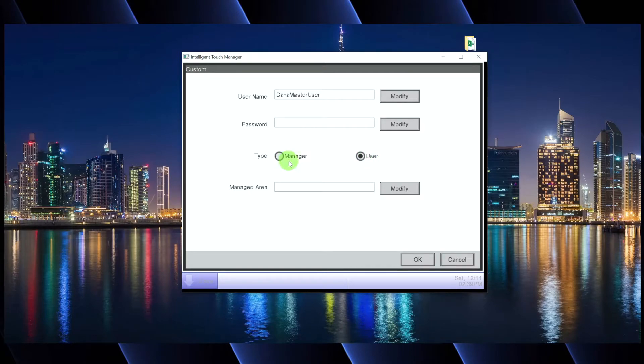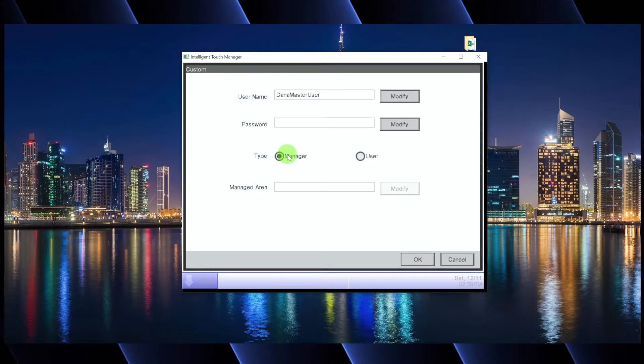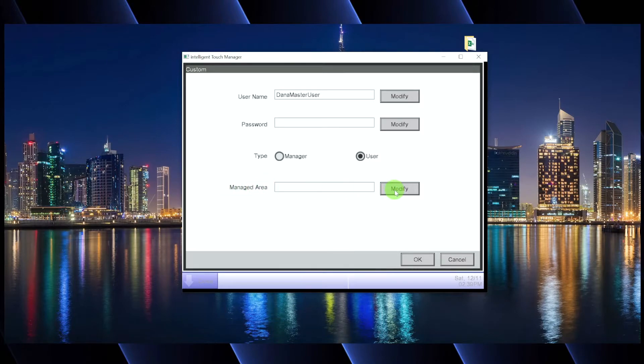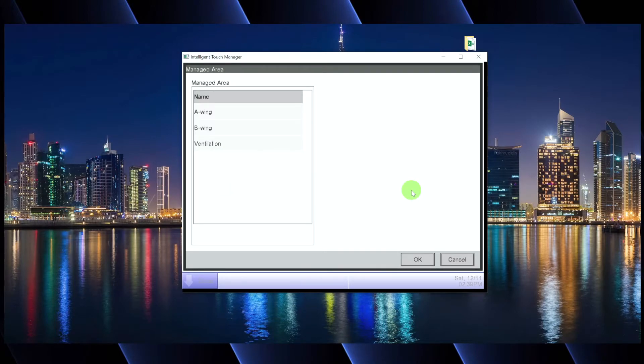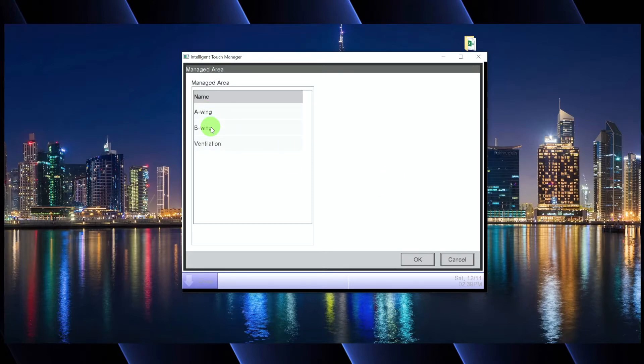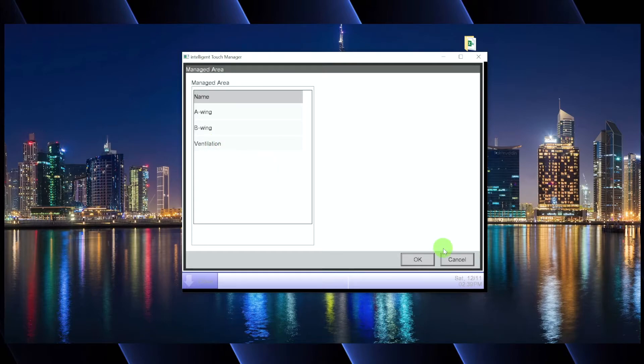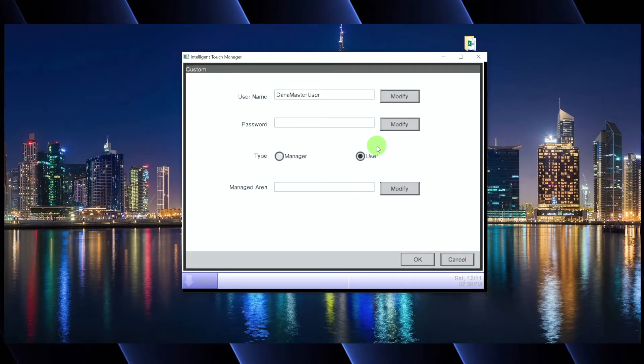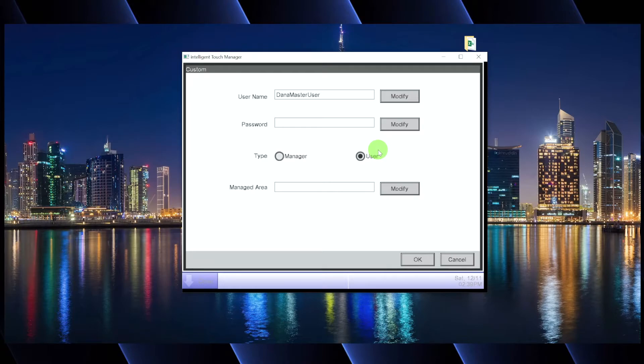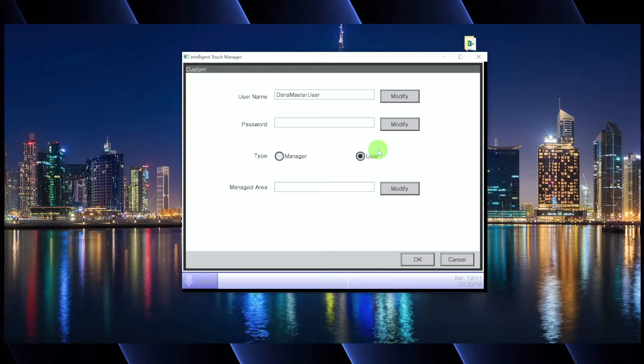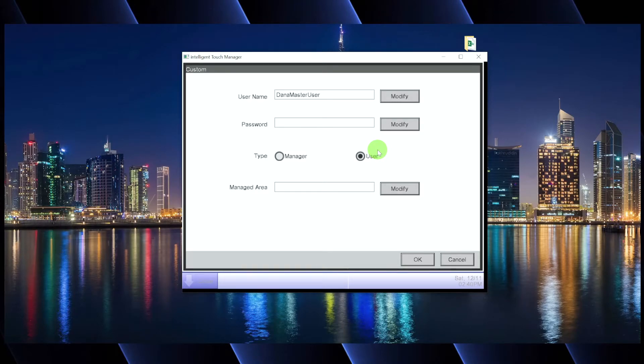Is this user a manager or a user? If they're a manager, they will have access to everything on the ITM. If they are just a user, then you're going to have to specify what area this user has access to. Does this user have access to the A wing, the B wing or the ventilation equipment, the ERV often what you'll do, or often what we've done in the past for like a college campus where we have a VRF installed in all the dorms is we can actually set up each kid, each college student's room with a remote access account so that they can actually go online and they can change the settings from pretty much anywhere in the world. And that's a very neat feature the ITM offers.